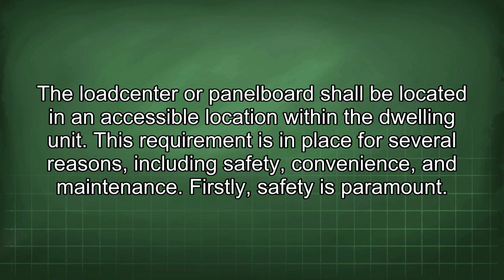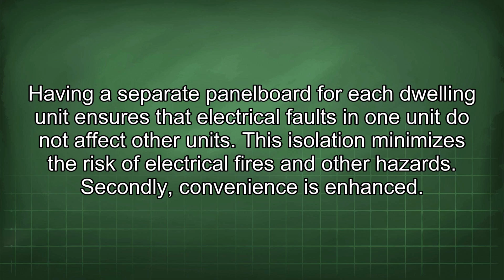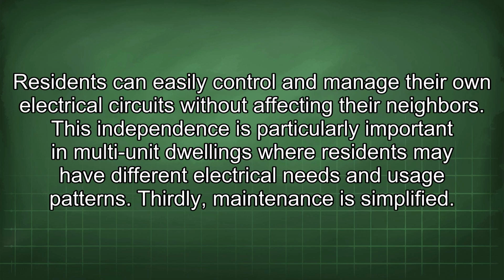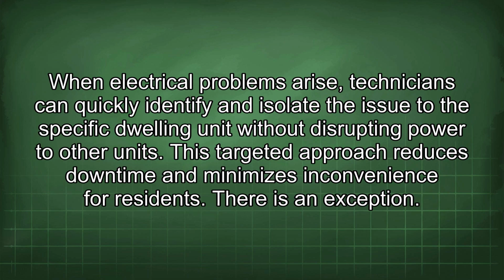Firstly, safety is paramount. Having a separate panel board for each dwelling unit ensures that electrical faults in one unit do not affect other units. This isolation minimizes the risk of electrical fires and other hazards. Secondly, convenience is enhanced. Residents can easily control and manage their own electrical circuits without affecting their neighbors. This independence is particularly important in multi-unit dwellings where residents may have different electrical needs and usage patterns. Thirdly, maintenance is simplified. When electrical problems arise, technicians can quickly identify and isolate the issue to the specific dwelling unit without disrupting power to other units. This targeted approach reduces downtime and minimizes inconvenience for residents.